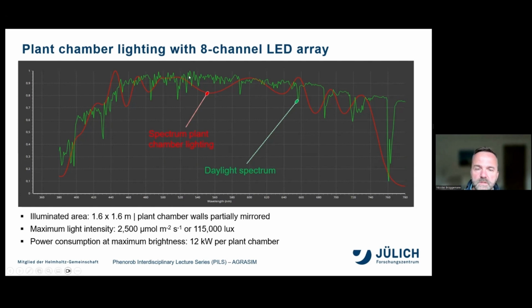But we also invested quite some effort to mimic the intermediate parts of the spectrum. And with these 8 channels, we now get quite close. You see in red here the spectrum of our lighting system, which mimics quite well the solar spectrum. There are some deviations, but that's hard to avoid. For this, you would need even more channels. And it's sometimes hard to get LEDs with a specific wavelength. For example, in this region of 670 nanometers, some LEDs are either not available or have only a short lifetime and so on. So you have to accept some compromises, but we were quite satisfied to be very close to the natural sunlight.